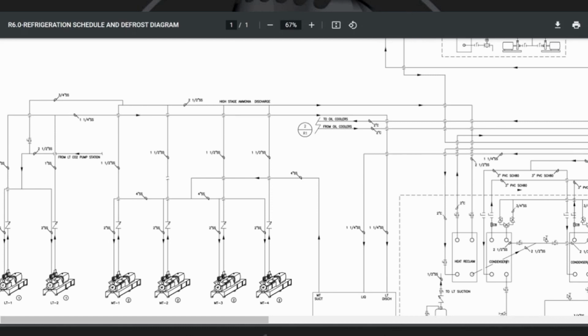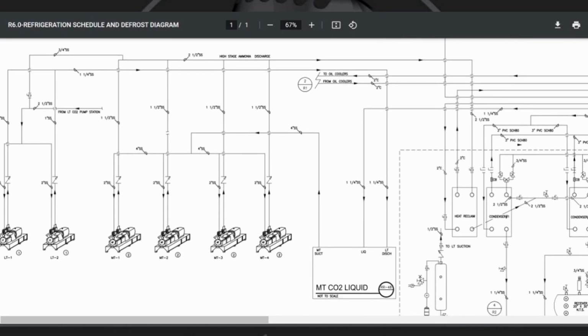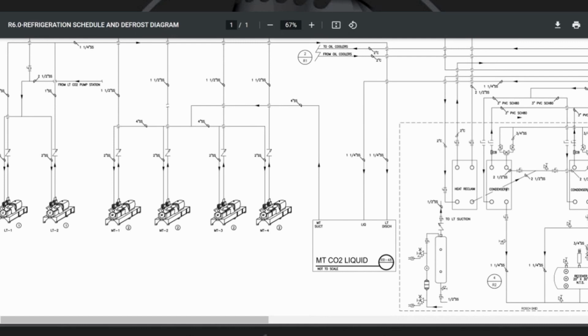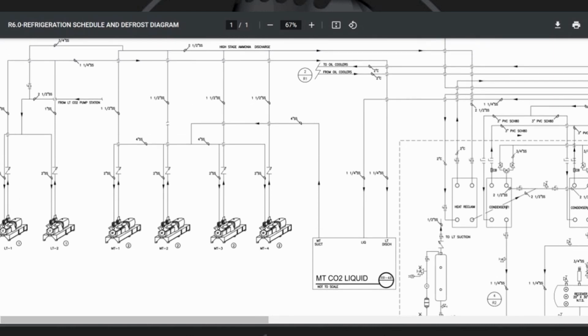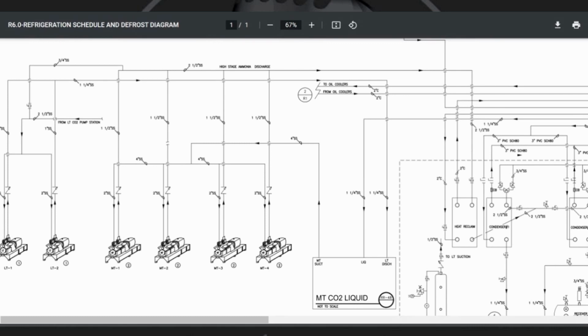So what about just going straight transcritical? Wouldn't that be a more viable option at this point with how much CO2 you guys have on site? It seems like transcritical would be a bit more efficient, especially if you're running those ambient temps all year round. Well, we don't have any experience with transcritical, but when we've talked to other people who have them, at least out here, the leak rate is about 100%. For some reason, something happens and they end up dumping their charge. So that's a concern. The other concern is all of the energy studies that have been done in our geographic area, where it gets to be 110, 115 pretty regularly.